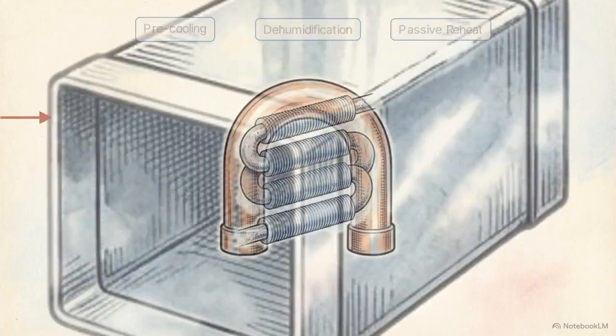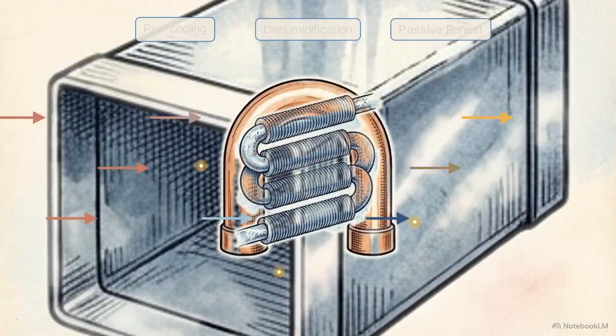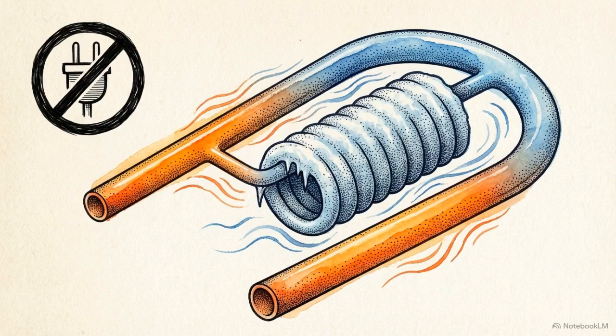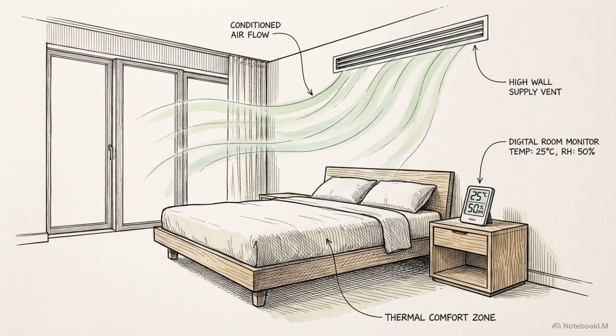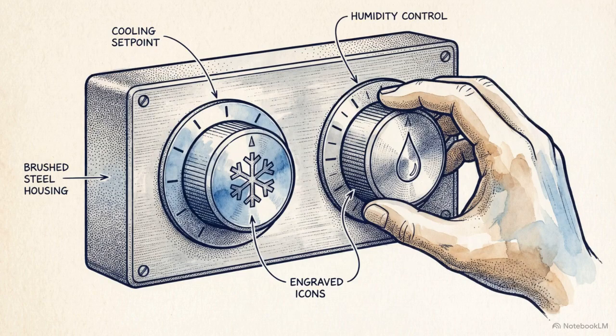A second passive hardware configuration is the wraparound heat pipe. It pre-cools incoming warm air across the pipe and transfers that exact thermal energy to post-heat the exiting air. The heat pipe leverages the incoming air's own thermal energy to execute the reheating phase, requiring zero additional compressor power. The mechanical output of either system is neutral temperature, fully dehumidified supply air that will not overcool the space. Active reheating transforms dehumidification from an accidental byproduct of cooling into a precisely controlled, independent variable.